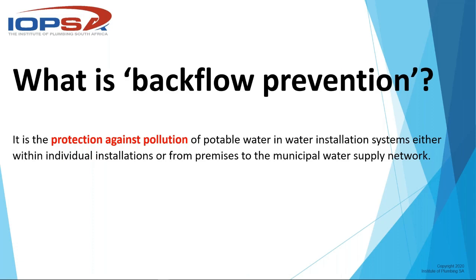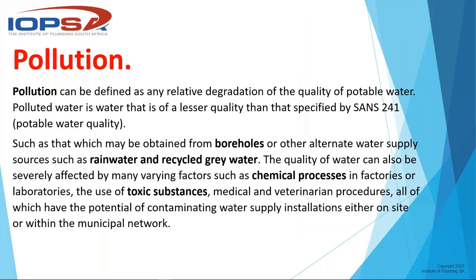Backflow prevention protects potable water in a water installation system, either within individual installations or from premises to the municipal water supply. Whether it be a house on a property or a complex, no water is allowed to flow back from an installation back into the municipal line. If we look at the definition of pollution, it can be defined as any relative degradation of the quality of potable water. Polluted water is water that is of a lesser quality than that specified by SANS 241.